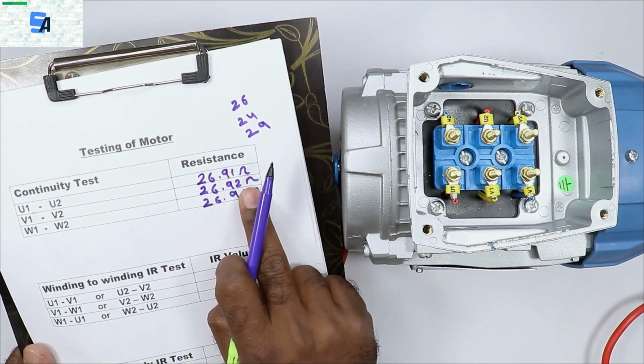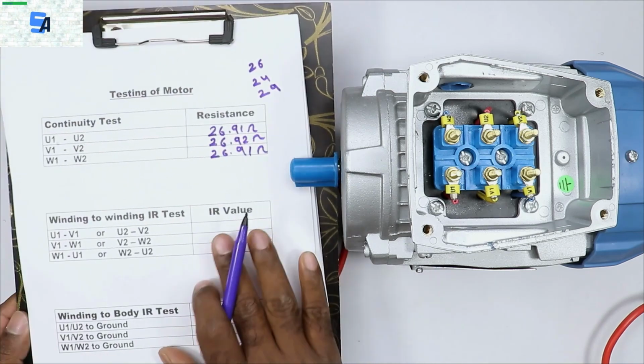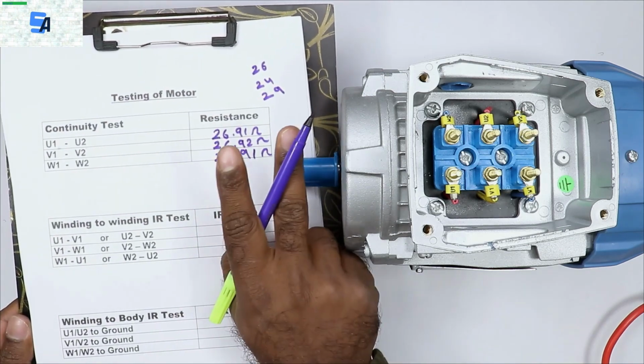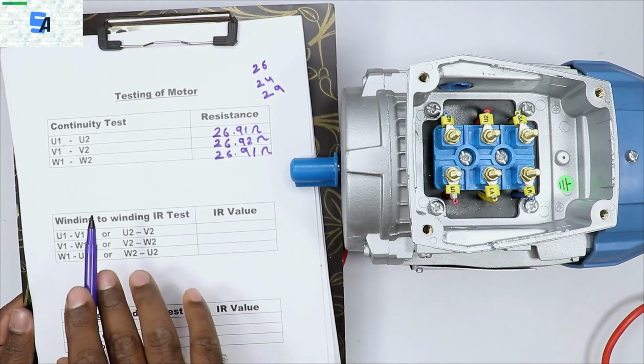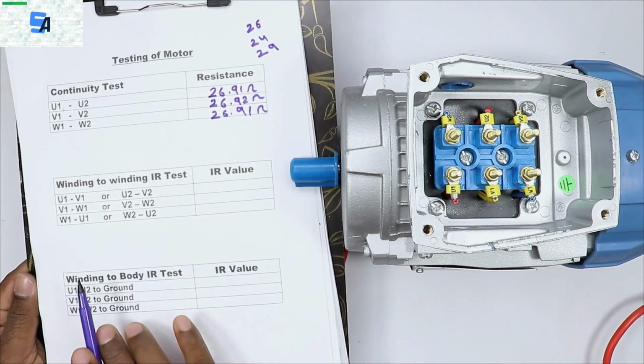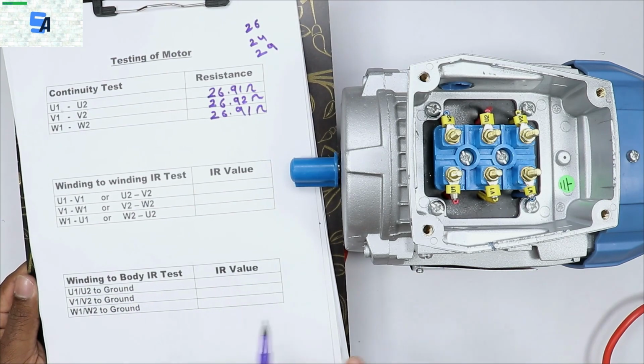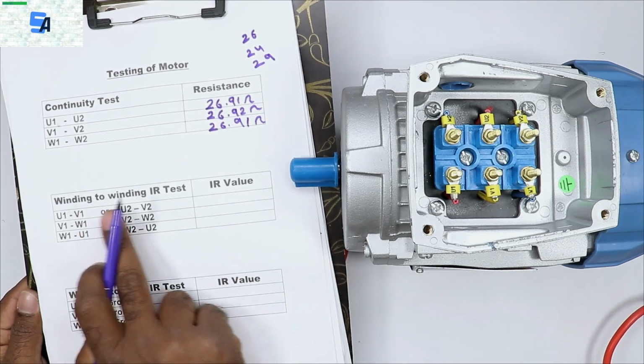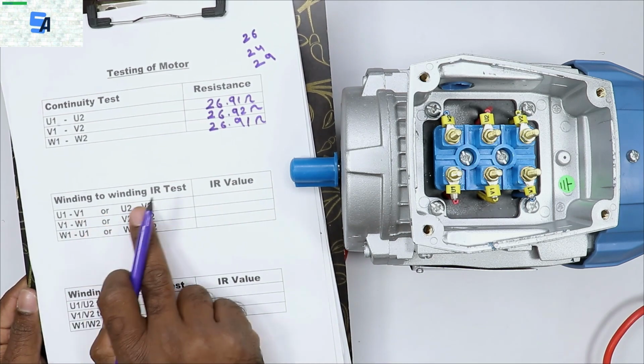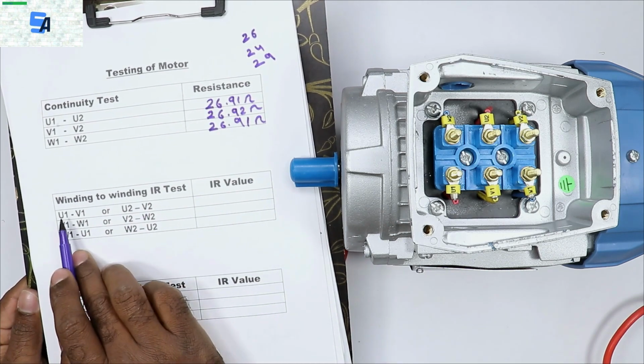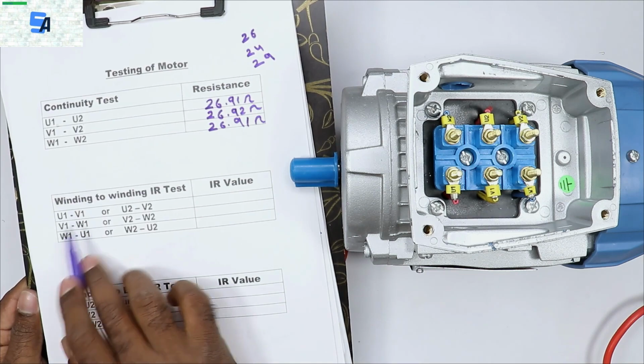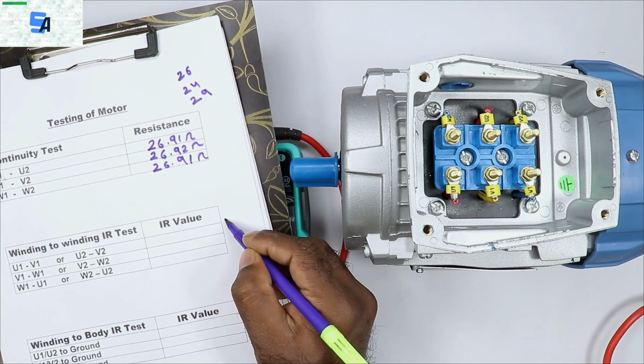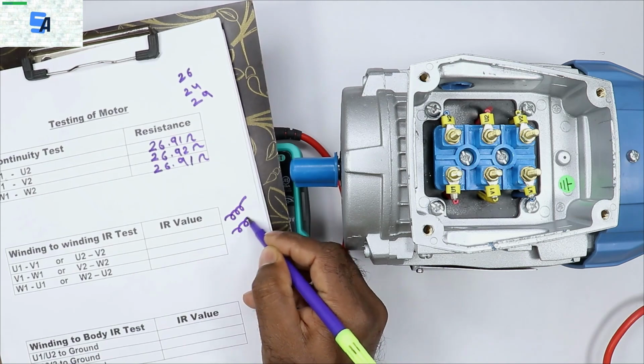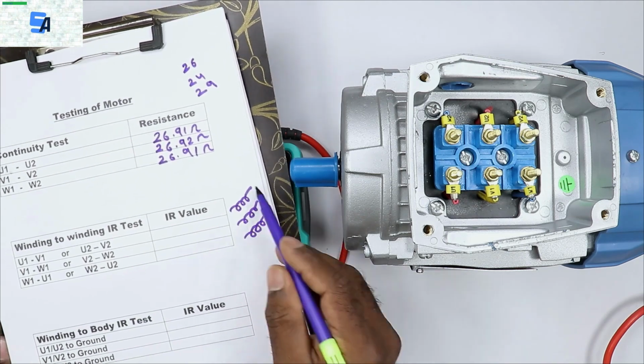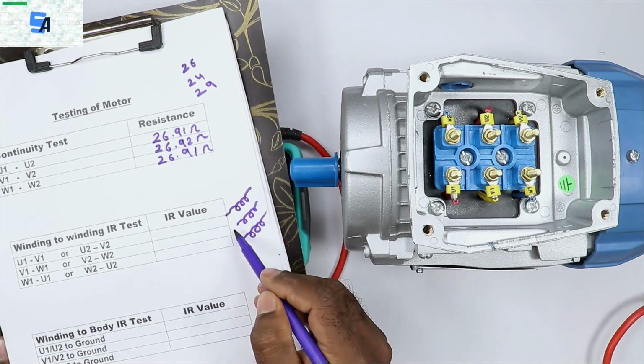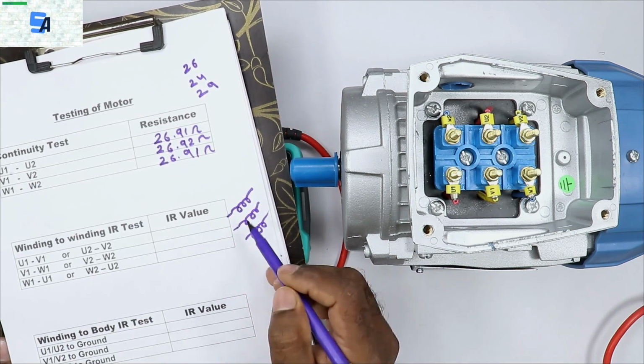After measuring resistance, we are going to measure the IR value. To measure the IR value, there are 2 ways. First, we can measure the IR value winding to winding. Second is the winding to body IR test. So first of all, we are doing the winding to winding IR test. For this, we have to measure between U1 and V1. It means inside the motor there are 3 windings. Among these 3 windings, between any 2 windings, we have to measure how much the insulation is.